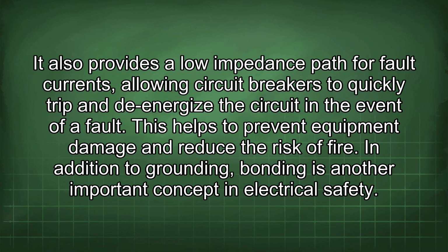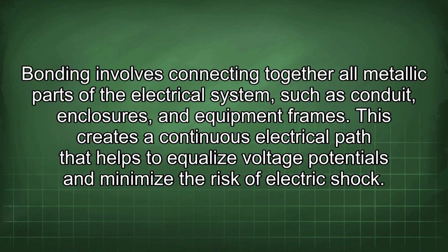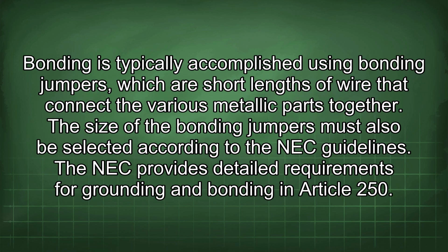In addition to grounding, bonding is another important concept in electrical safety. Bonding involves connecting together all metallic parts of the electrical system, such as conduit, enclosures, and equipment frames. This creates a continuous electrical path that helps to equalize voltage potentials and minimize the risk of electric shock. Bonding is typically accomplished using bonding jumpers, which are short lengths of wire that connect the various metallic parts together. The size of the bonding jumpers must also be selected according to the NEC guidelines.